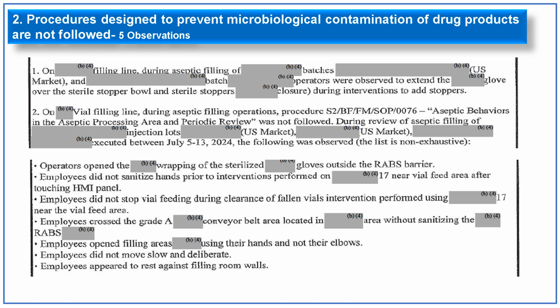Second observation: there were multiple examples that the aseptic processing areas and periodic review of aseptic behavior SOP was not followed. This includes that an operator opened the wrapping of the sterile glove outside the RABS barrier. Employees did not sanitize their hands prior to interventions performed near the vial feed area after touching the HMI panel. Employees did not stop the vial feeding during clearance of fallen vials. An employee crossed the grade A conveyor belt area without sanitizing the RABS. Employees opened the filling areas using their hands and not the elbows. Employees did not move slow and deliberate. Employees appeared to rest against the filling room walls.